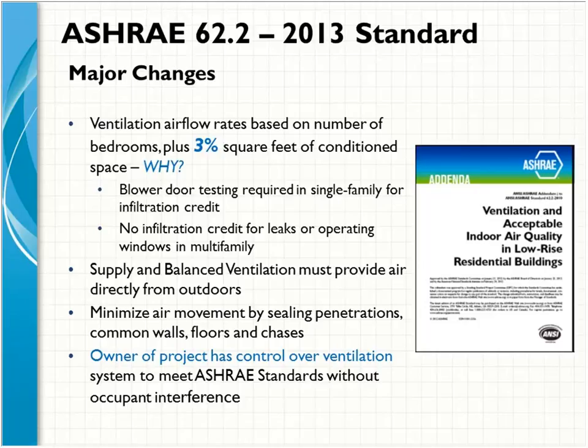One thing I should point out, though, and you see it's highlighted there near the bottom of the slide, is that the owner has control over the ventilation system. And of course, in a single-family home, that's going to be the owner, if it's an owner-occupied single-family home. But in a multifamily situation, the building owner is the person with the investment there, and occupants will often disable ventilation and create a situation that might be damaging to the building by not removing moisture, and also deteriorate their own indoor air quality living space. It's important that the owner have control over that system so that they can protect their investment and, hopefully, create an indoor air quality situation that's better for the occupants in the multifamily.